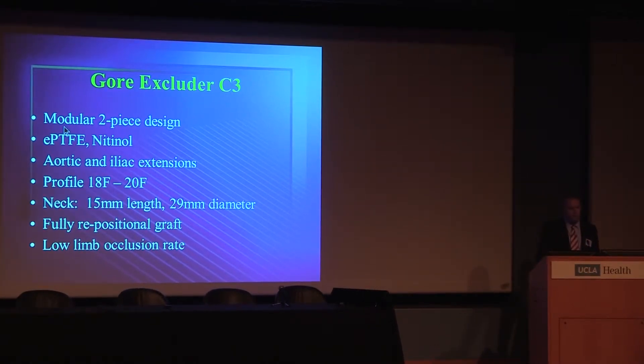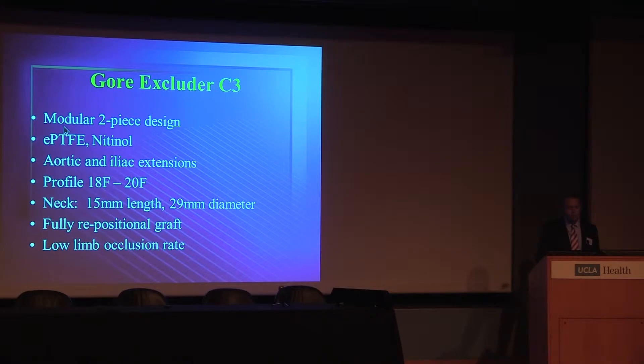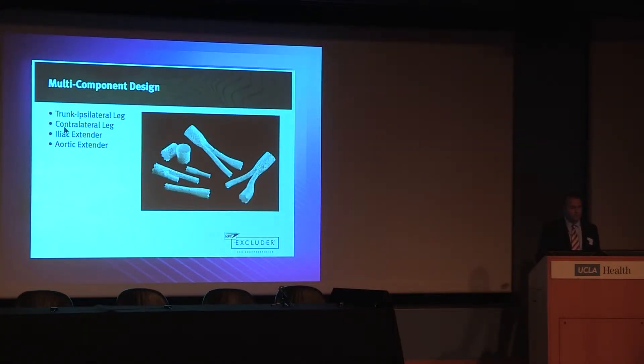The Gore C3 Excluder device is a tried-and-true, modular two-piece device made out of proprietary PTFE material bonded to a nitinol frame. It has aortic and iliac extenders and goes through a standard 18 to 20 French sheath delivery system. The IFU is for a 15-millimeter length and a 29-millimeter diameter neck. The unique component is that it is fully repositionable — the only fully repositionable device that can be moved either cranially or caudally, with deliverable limbs including ipsilateral trunk and leg, contralateral legs, and extenders for both iliac and aortic components.